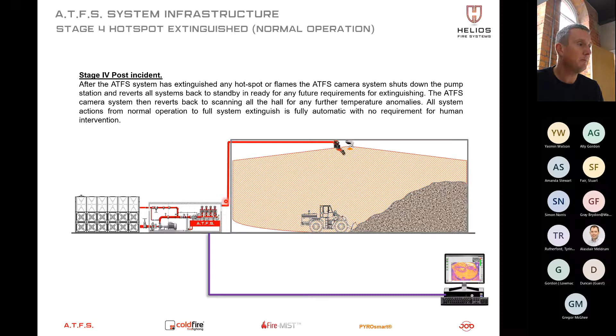And part of the SOP is, let's say this happened at 2 o'clock in the morning and there was nobody there. The first operative who goes to site will go to the screen first. Is that fire out? Yes, that fire's out. Okay. Are there any other hotspots that I can see? No, there's not. He will then make his way to the pump station and switch the pump off. We don't need this pump running for any longer than it needs to, so we're not running against deadhead. We actually run the water back through the test loop to ensure that we're circulating the water to the water tank. But if a fire was to start again up here, then the pump system would automatically fire up and start fighting the fire again.